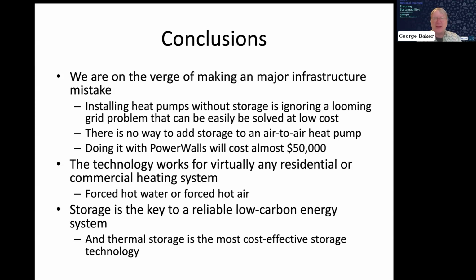We're installing lots of air-to-air heat pumps, but there's no way to add storage to an air-to-air heat pump. Samantha was completely right: if you use your heat pump to make hot water, you can use it in a hydronic heating system, or in a forced hot air system by simply putting a heat exchanger in the plenum. If you start with an air-to-water heat pump, you can use any existing distribution system.